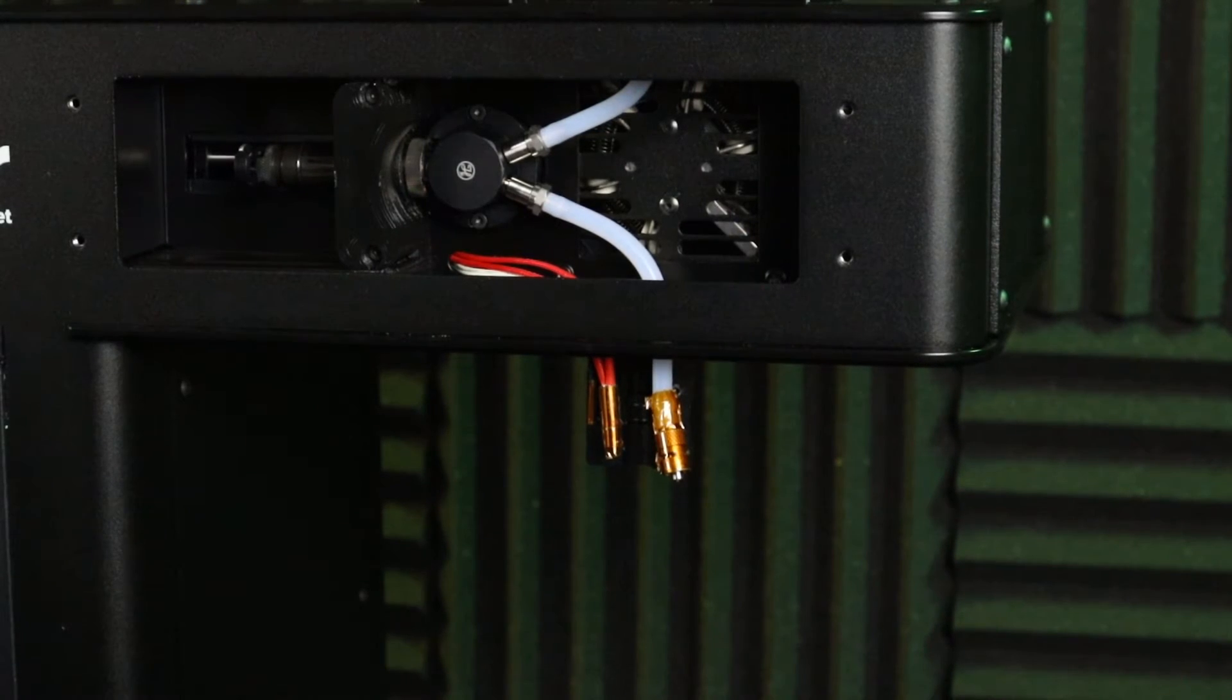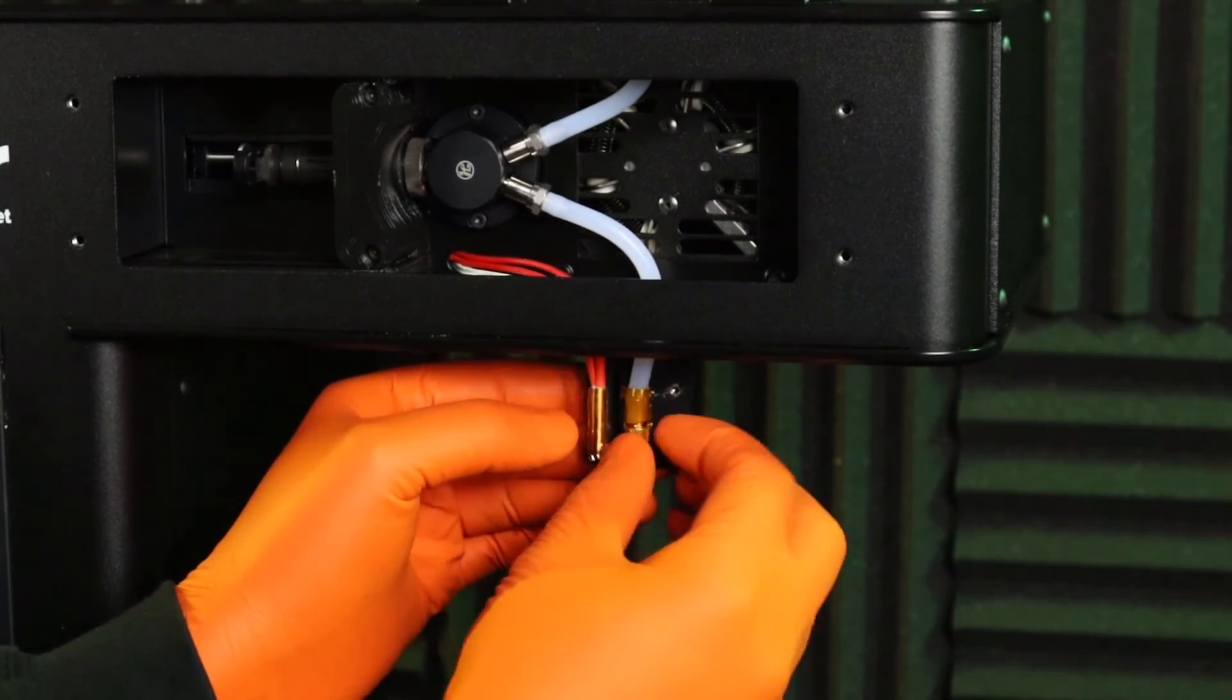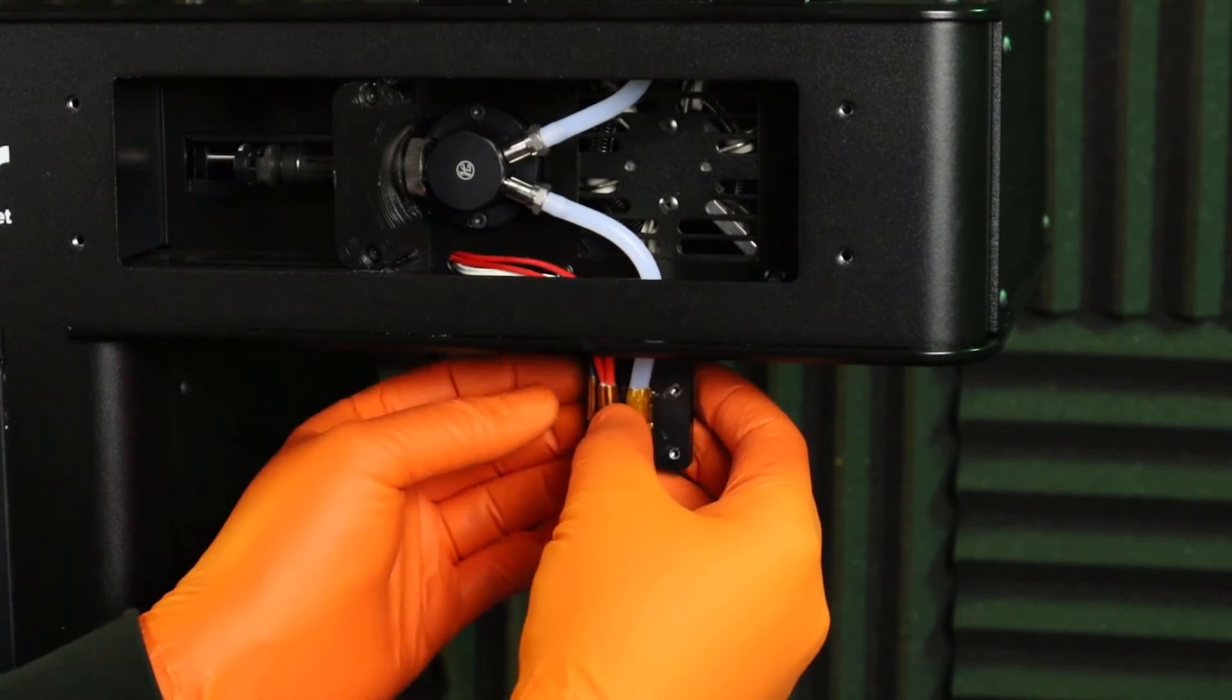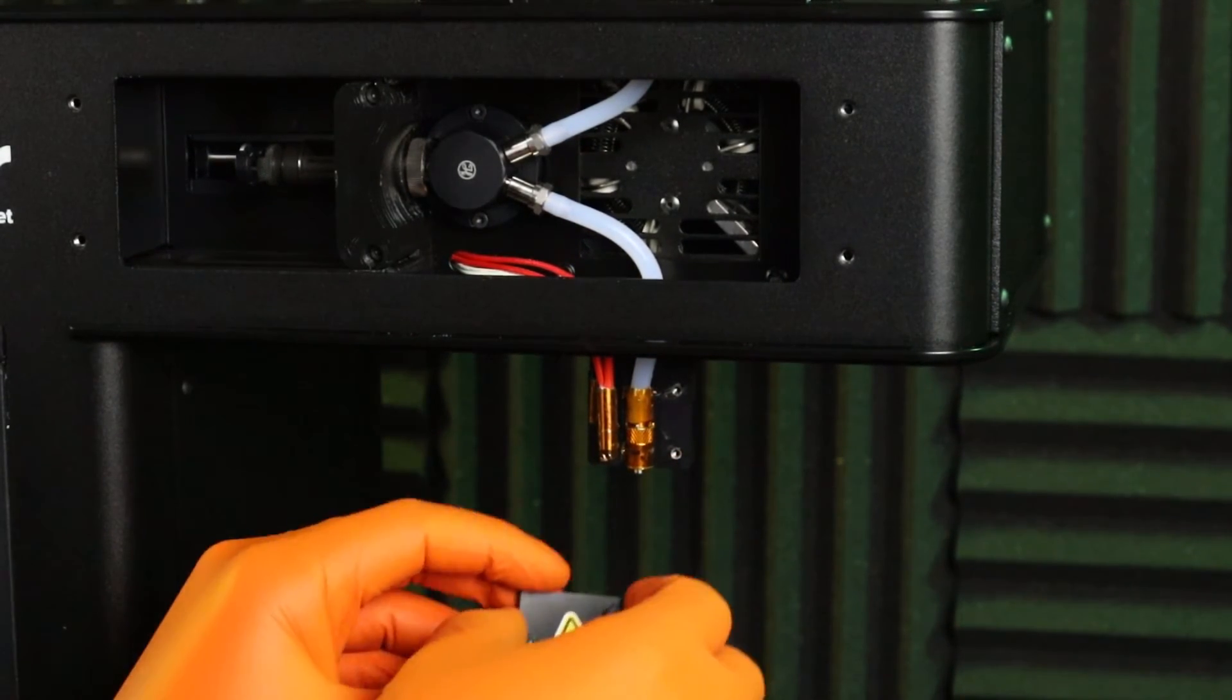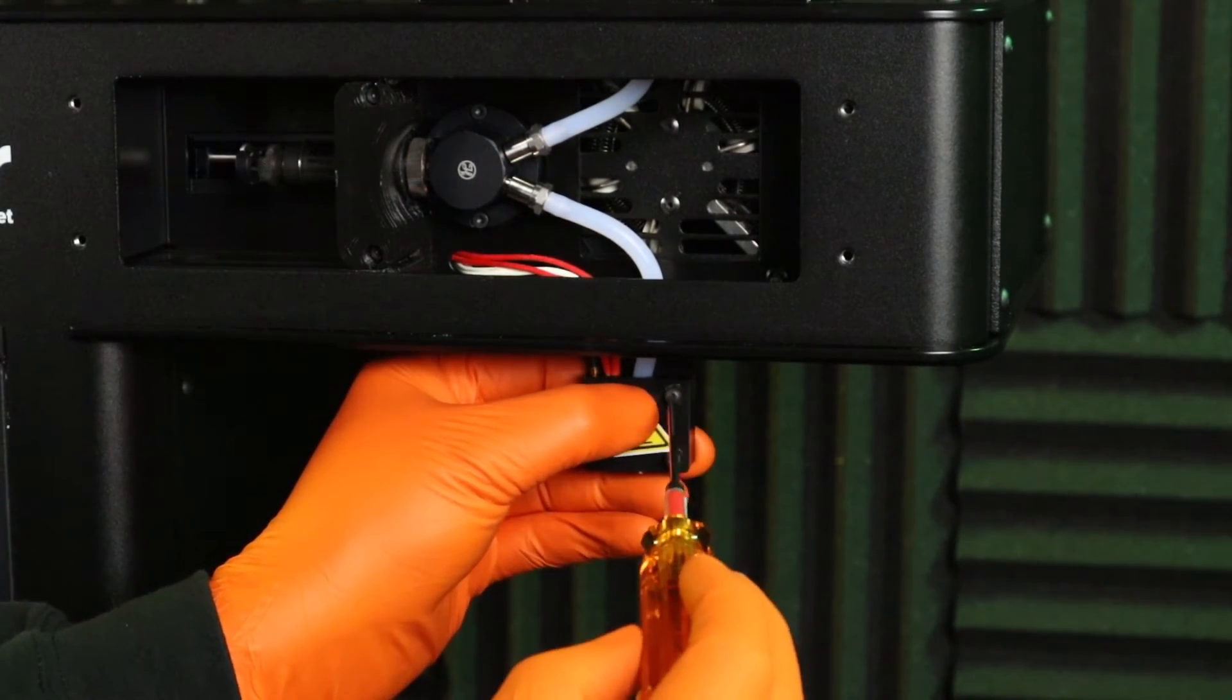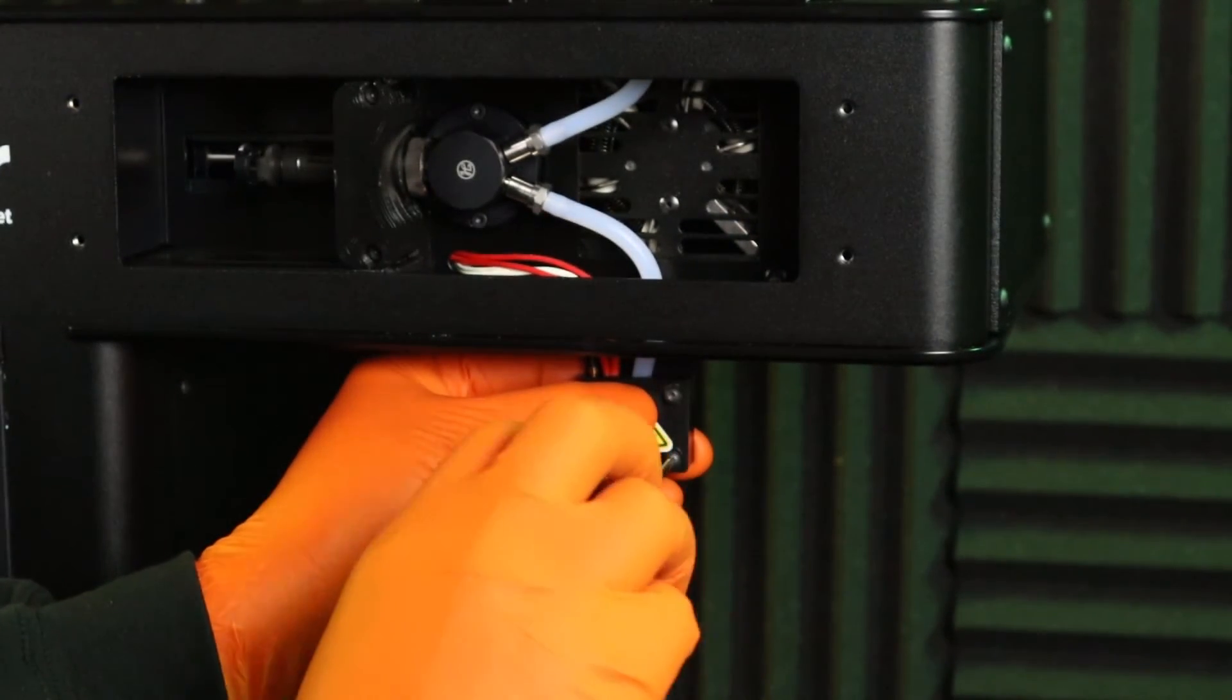Next, we're going to reassemble the luer lock heat block. First, place the PTFE and luer lock barb adapter into the slotted and grooved space in the heat block. Seat the red needle heater and black thermistor wire ends into their respective slots. Hold all three in place while putting the heat block cover back on. Using the 2 millimeter hexagonal driver, start by inserting the two screws on the right.